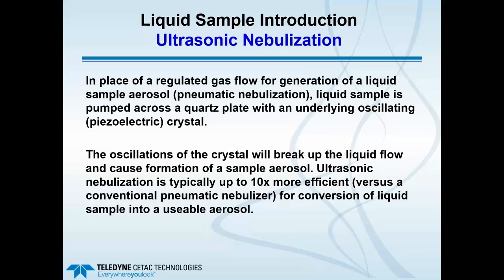How does the ultrasonic nebulizer work? In place of a regulated gas flow for generation of a liquid sample aerosol — such as a pneumatic nebulizer like a glass concentric, cross-flow, or V-groove nebulizer — in this case the liquid sample is pumped across a quartz plate with an underlying oscillating piezoelectric crystal. An electrical signal applied to the crystal imparts a mechanical signal that breaks up the aerosol, causing the formation of a more efficient aerosol — up to about 10 times more efficient than a conventional pneumatic nebulizer.